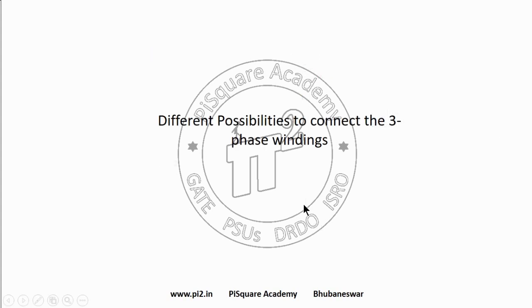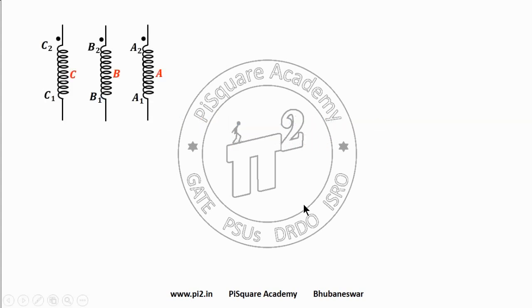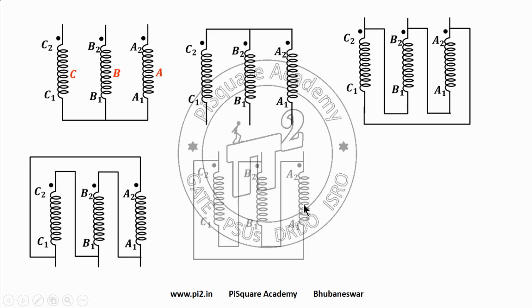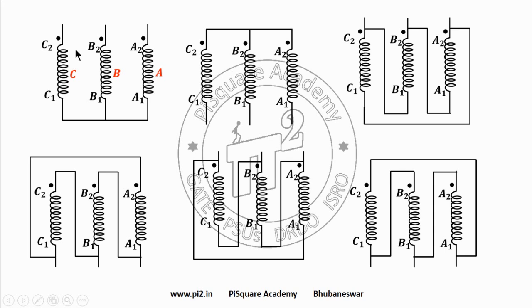Now let us see different possibilities to connect three-phase windings. We have three coils — they can be connected in star or delta. If you notice, it is not just these two; we can have even more. This is also a star and this is also a star, but these two are different. Here the connection terminals are A2, B2, C2, while here they are A1, B1, C1. And if you see the delta configurations, they are different from each other though they are all delta. So we can have 6 distinct configurations of a three-phase connection.